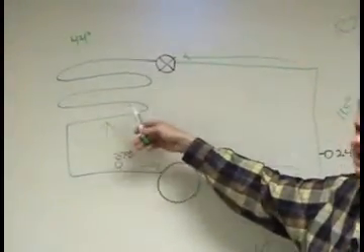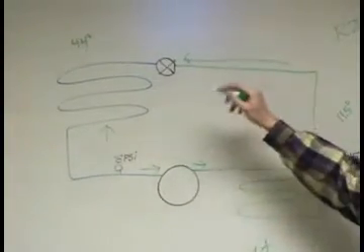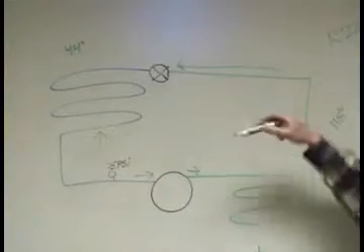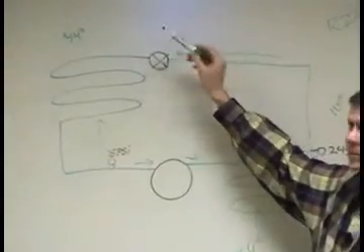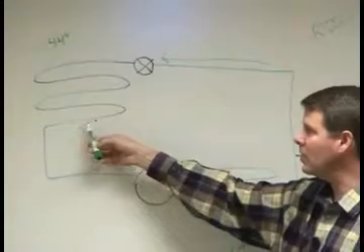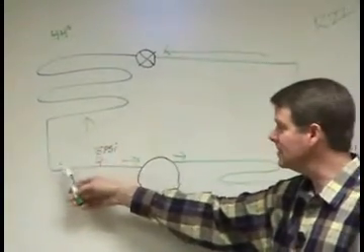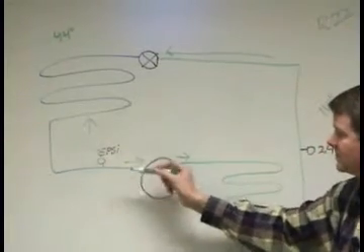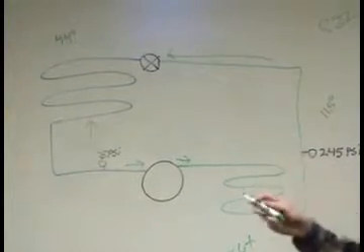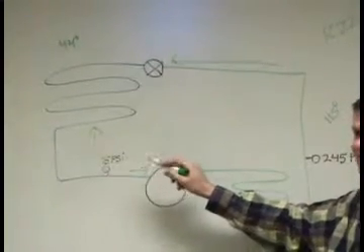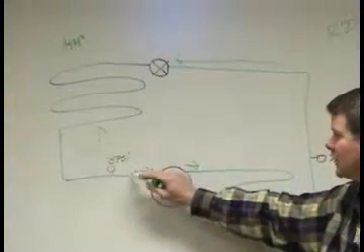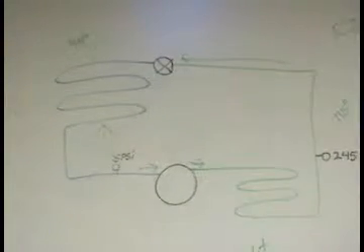So it is absorbing the heat out of that 76-degree air, probably going to drop it, normal is like 15 to 18 degrees, that air temperature. So now we've got cold air blowing into your house. We've got this liquid coming back. It's completely boiled off, probably warmed up a few degrees, but it comes back at 75 pounds, and it's fairly cool. It's no warmer than the 76 degrees blowing across it. So it comes back here pretty cool. It's probably going to be 50, 60 degrees, enters back into the compressor where we start over.